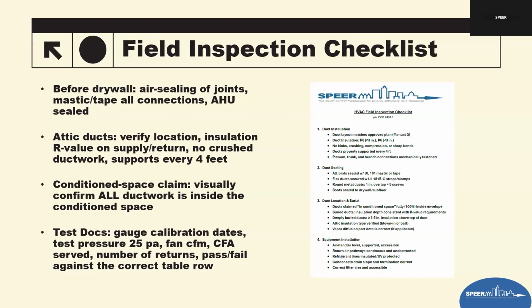So now with the new table that we have, it's going to be very important to say what the CFM per 100 square feet was, not just what the CFM was. List the conditioned floor area being served and the number of returns that system has. The targets in the table we saw are listed by number of returns for the house, but you want to know, for the one system you just tested, how many returns it had. And then, of course, whether the pass or fail result matches the row on that table.